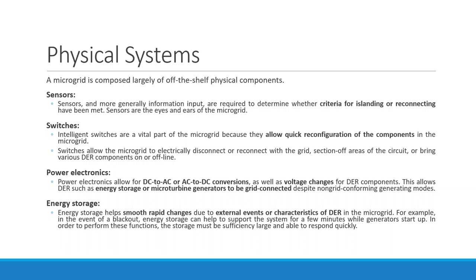Then the physical system will have the switches. These will be intelligent switches, which are considered a vital part of the microgrid, because they allow quick reconfiguration of the components in the microgrid. Reconfiguration means things can be connected or disconnected. When you disconnect something from a particular system, that is a reconfiguration, and when you connect something, that is too. So these intelligent switches allow the microgrid to electrically disconnect or reconnect with the grid. A particular section or area of the circuit can be disconnected or reconnected, and various distributed energy resources components can be brought on or offline. So if the microgrid consists of a battery, wind, and solar, a particular part can be connected or disconnected using these intelligent switches.